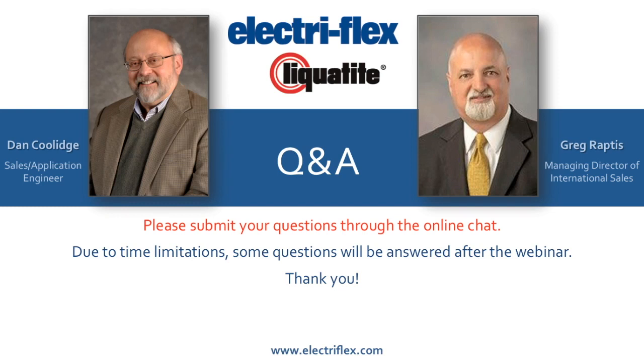Why would I need a UL listed conduit if you offer a non-UL? I get this question asked of me all the time. A UL listed conduit is generally required for installations in the field where it must meet certain code requirements such as the NEC. Many inspectors insist on this. There are industries, however, not covered by the code, such as mining, transit, and power utilities, plus some machinery builders. Although these industries set up their own requirements, they may allow non-UL listed products to be used.